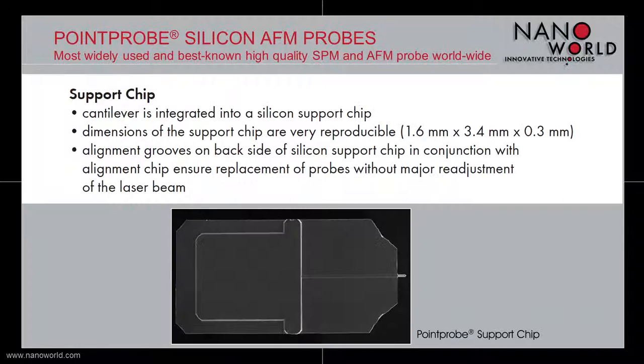The cantilever of our Pointprobe probes is integrated into a silicon support chip. The support chip is 1.6 mm wide, 3.4 mm long, and 300 micrometres thick, and has integrated alignment grooves on its backside. These grooves ensure replacement of our probes without major readjustment of the laser beam.